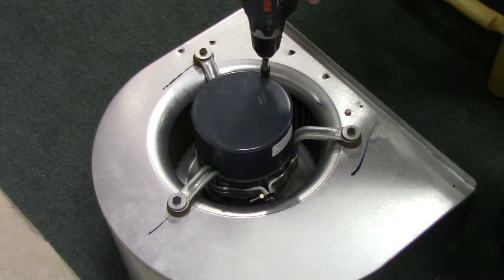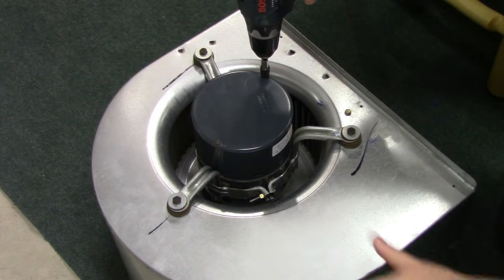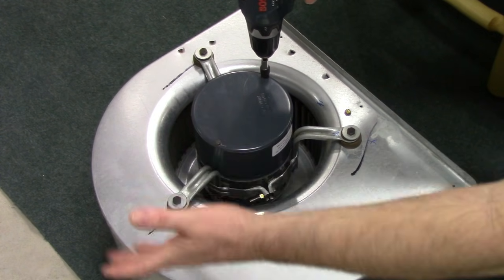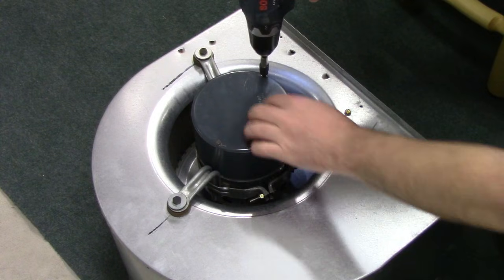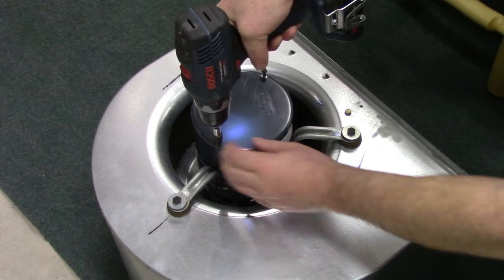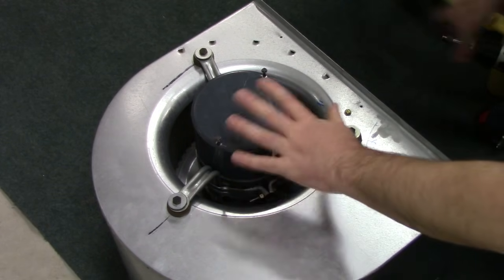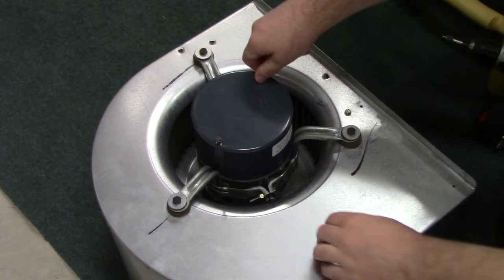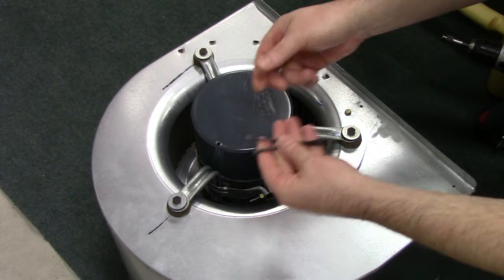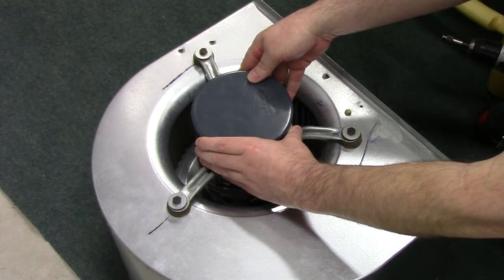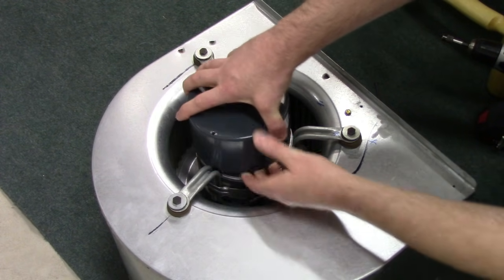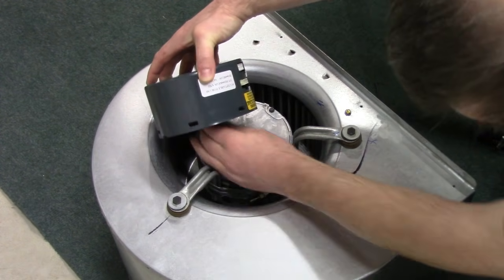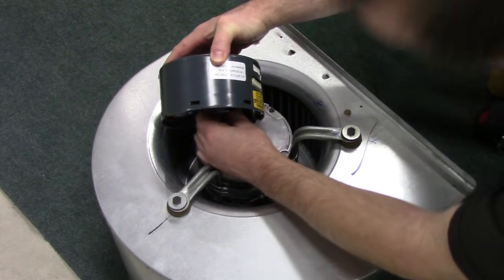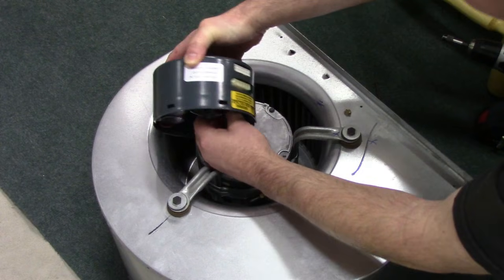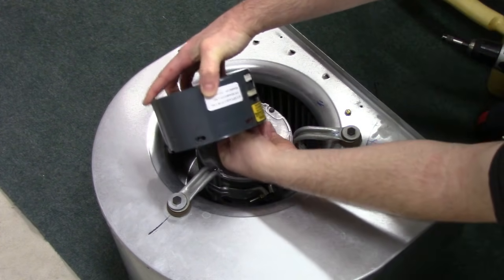So with the blower assembly out, we can get at the ECM here. Now, I've already looked, I've got the actual repair or service manual for this furnace. You can find them online. And they say to check these. Before you can condemn either the ECM or the motor, you have to do a couple of checks. But to get the ECM out, you just take these two long bolts out. This will lift off of the back of the motor. And there is a little wire, well, it's a 3-prong wire. You have to take that out. There's a little plug in here. Come on, you little rascal.